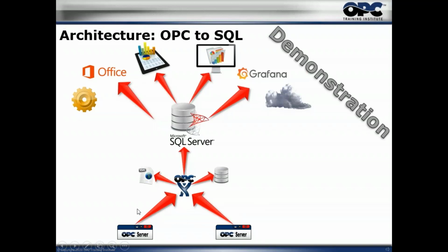Well, in that case, you can use the data queue that's built into OPC UA. This data queue enables you to actually retrieve data that you wouldn't have received if the problem is a network disconnection. So the OPC server can actually queue up the data, and OPC Expert will grab this data and send it to SQL Server. So that's handled with the data queue, which is handled by the OPC server.